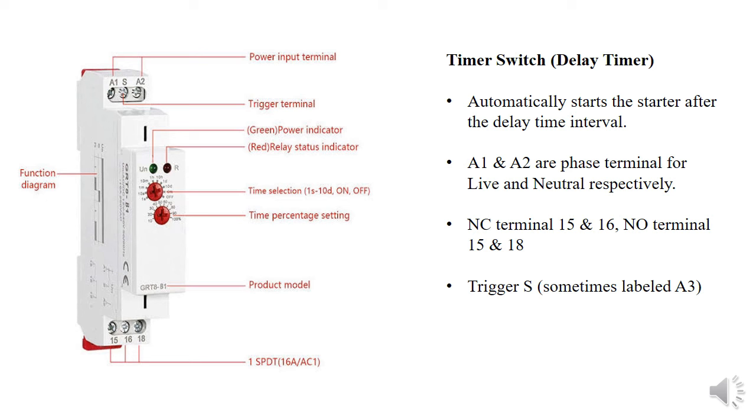The delay timer or timer switch allows the starter to operate at a given interval — for example, set to operate in 30 minutes, it will start automatically after that time. It has six terminals: A1 and A2 are for the phase line or single-phase connection (live and neutral). Terminal S, sometimes labeled A3, is the trigger terminal. Terminal 15 is the common, which works with terminal 16 for normally closed, or with terminal 18 for normally open.